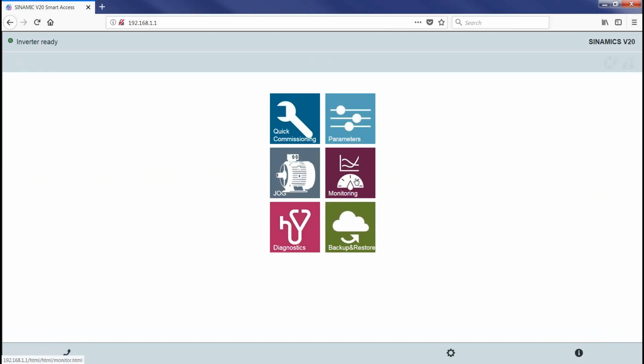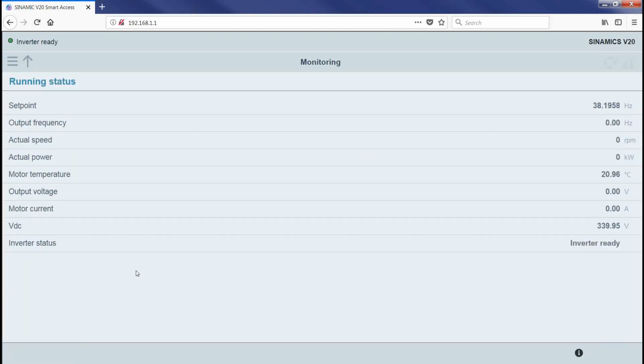All right, now I'm going to go back up a level. Next is monitoring. So same parameters we showed in the presentation. So I've got a potentiometer, so we see the set point here. I can turn the set point down, so 0 hertz, or I can scroll up to 60, or just shy. So again, I'm going to go to about 30, and then I'm going to start it with my selector switch. So again, we can see set point, output frequency takes a little time to ramp up. Remember, 10-second accel time. Actual speed in RPMs, power in kilowatts, motor temperature, the output voltage. So in a volts to hertz ratio there, the voltage increases with the frequency and decreases with the frequency.